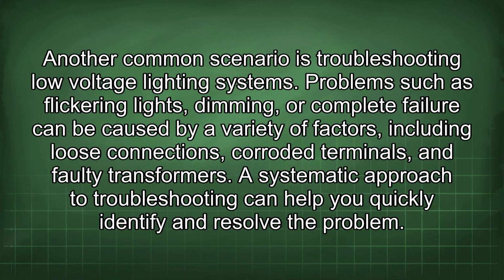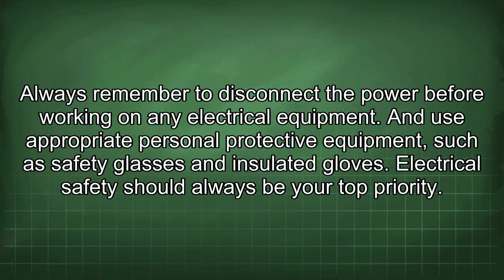Another common scenario is troubleshooting a low-voltage lighting system. Problems such as flickering lights, dimming, or complete failure can be caused by a variety of factors, including loose connections, corroded terminals, and faulty transformers. A systematic approach to troubleshooting can help you quickly identify and resolve the problem. Always remember to disconnect the power before working on any electrical equipment, and use appropriate personal protective equipment, such as safety glasses and insulated gloves. Electrical safety should always be your top priority.